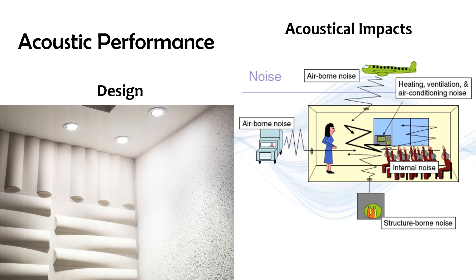The last credit is for one point for acoustic performance. The intent is to design workspace and classrooms with effective acoustics. You can ensure the noise levels are appropriate in at least two areas: HVAC background noise, sound transmission, or reverberation time. HVAC background noise must have levels in accordance with the ASHRAE handbook. For sound transmission, you need to meet building code or composite sound transmission class (CSTC) ratings. Reverberation time can be considered for spaces in hotels, office buildings, courtrooms, performing arts spaces, labs, houses of worship, libraries, stadiums, and gyms. You need to consider the acoustical impacts of interior finishes, building geometry, and duct insulation.